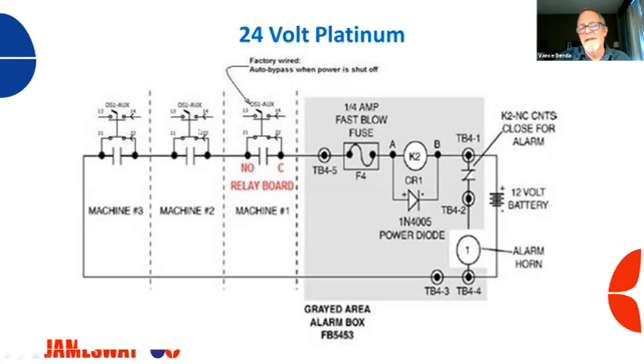But on our previous machines, you notice in the diagrams I showed you, there was actually a manual bypass switch, which means on those machines, when you disconnect power to the machine, you had to do a two-step process. You had to shut the disconnect off and turn the alarm bypass on. Our 24-volt platinum, the alarm bypass is actually mechanically connected to the main power disconnect. So anytime you walk up to a 24-volt platinum and shut the power down, you're automatically bypassing it. Pretty handy and good thing to know.